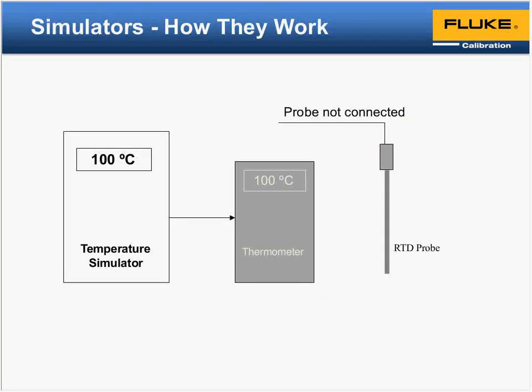In this scenario, the first one we were kind of showing 0. This one is similar, but we're down on the flip side of the 100 degrees C. So again, we've removed the probe piece, whether it be an RTD or thermocouple. Folks will even just simulate resistance if they're using resistor measurements. But basically, we're now the simulator to the thermometer. We're going to have a good connection, and then we're going to simulate the temperature desired. Typically at this point, not to jump too far ahead of ourselves, but this is kind of the first piece in recording your as found data.